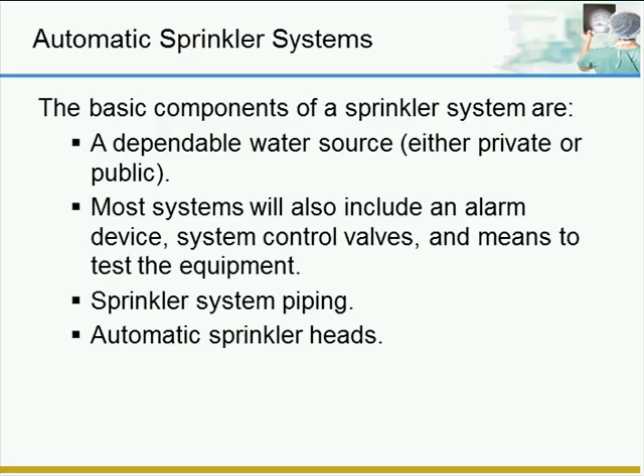Here are some basic components for a sprinkler system. First thing you will need is a dependable water source, either a private source from a pond or an underground tank or an above ground tank, or more commonly, a public water supply. And this would be the piping from the main in the street into the riser within the building. And I'll be going over some of these terms in a few moments. Most systems include an alarm valve or a control valve and a means to test the equipment. The equipment that most people are familiar with is the sprinkler piping overhead or buried in the ceiling and the actual automatic sprinkler heads that you can see in your occupancy.